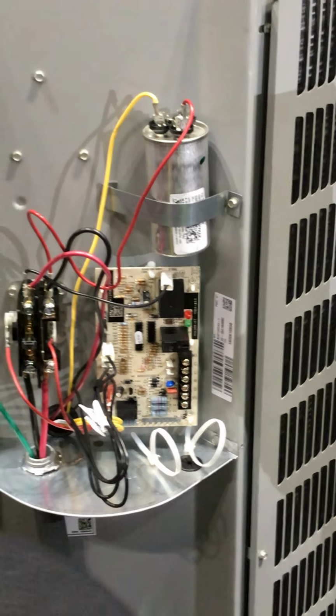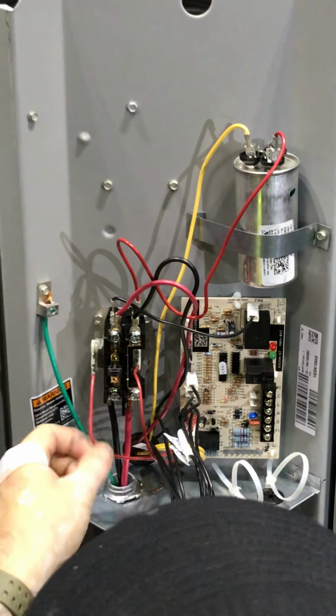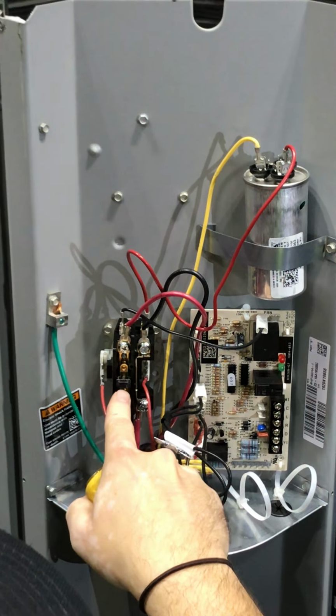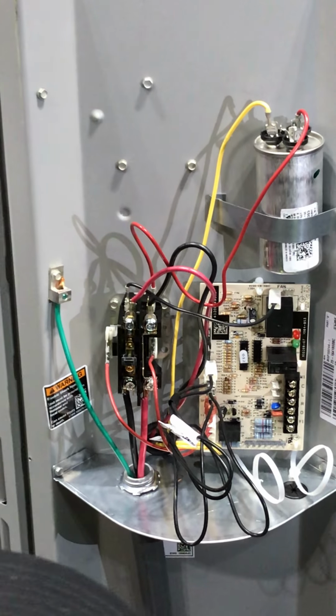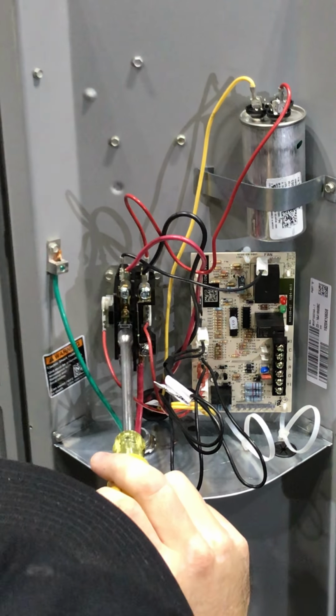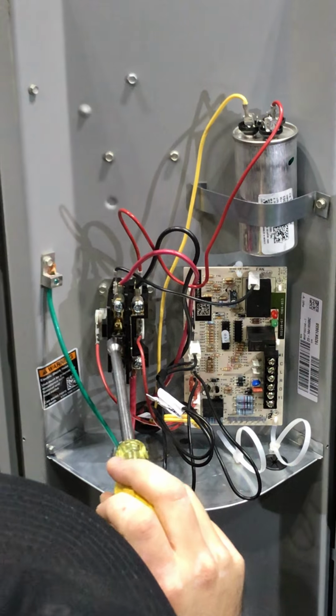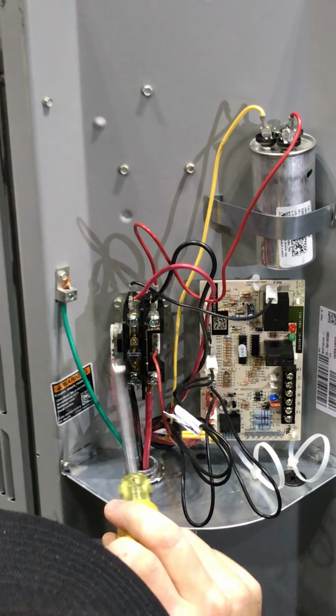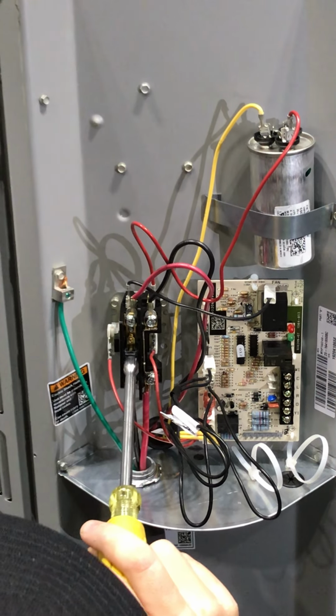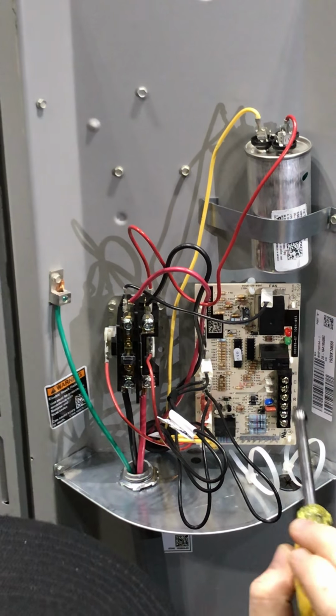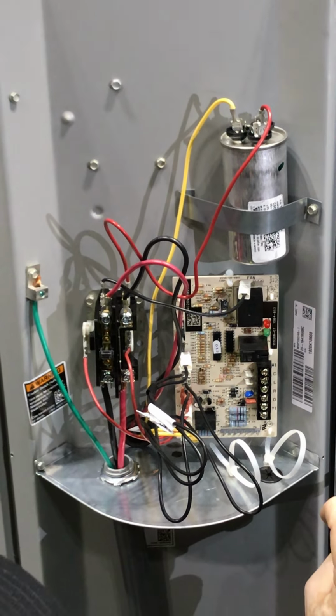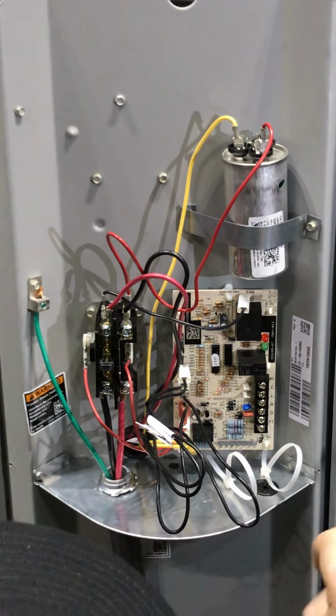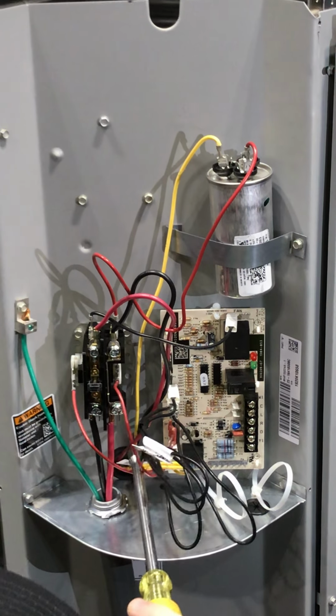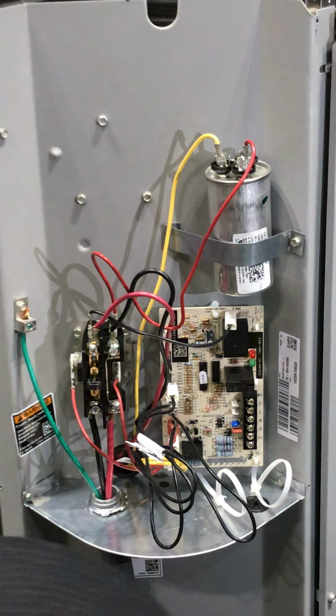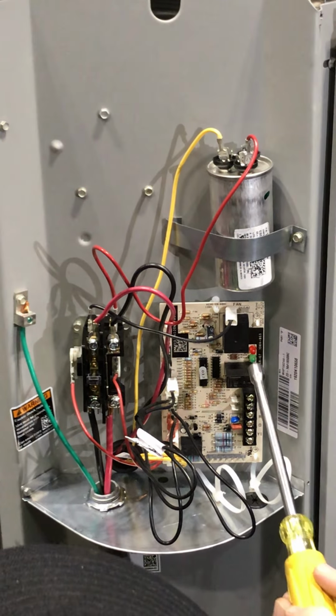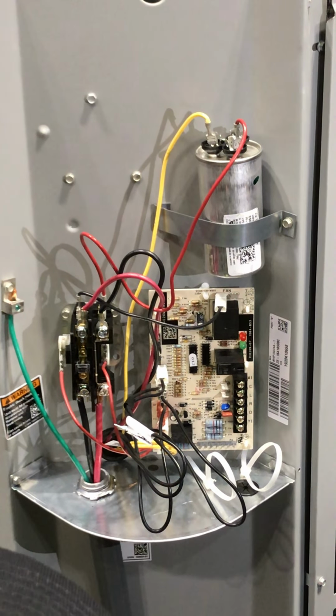So I would check my thermostat, Richard, and make sure that my connections are nice and solid and not loose, because these are what engage this. You can press on this contactor. It's not live? I personally would recommend a screwdriver to engage this, because that is 240 volts. If you engage this and it turns on, that means the problem is your 24 volts, your low voltage. If this is not engaged, it's your 24 volts, which come from your control board to your thermostat. So that's where you would go to troubleshoot. You'd start from your thermostat and work your way back here. If everything looks good, connected and solid, and that's still not engaging, maybe you have a bad thermostat, maybe a bad defrost board, maybe one bad wire somewhere in your air handler that you haven't checked yet.